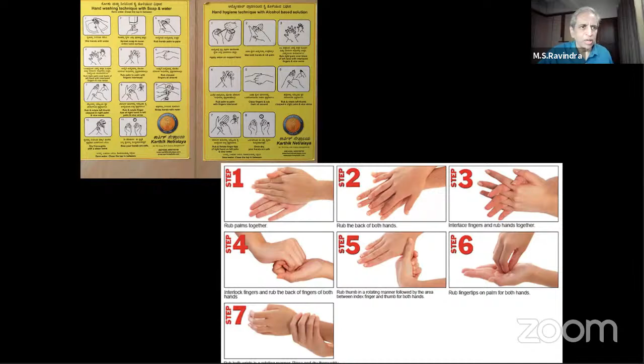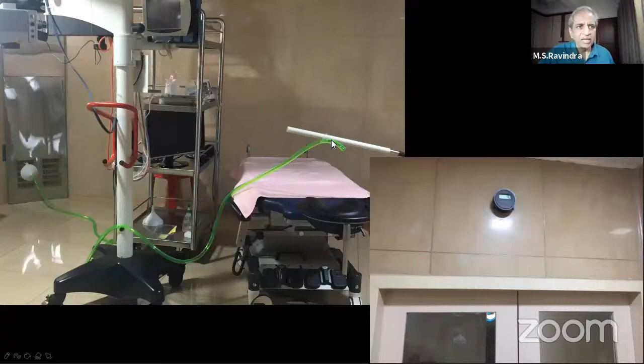Before you enter any chamber, either your OT or otherwise, you have to keep your hands absolutely clean. And that's the OT, the operation theater. We have made a device. It's a 1-inch plastic pipe. The patient is going to lie down there. This plastic pipe is connected to the return air ducts of my operation theater AHU.